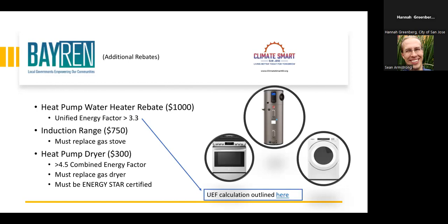It does not necessarily. If you could put it in the exact same closet where the gas water heater is, noting that heat pump water heaters are 21 inches wide and gas water heaters are generally 21 inches wide also, but sometimes they're narrower. So you could have a 30-gallon tank in a closet that was 18 inches wide. And if that closet was just 18 inches wide, you can't fit a heat pump water heater into it. So assuming you've got 21 inches at least, and really you'd like to have 30 inches so that a plumber can get their hands in there, but that's true for gas water heaters also. There's plumbing to install, not just slip a tank in.